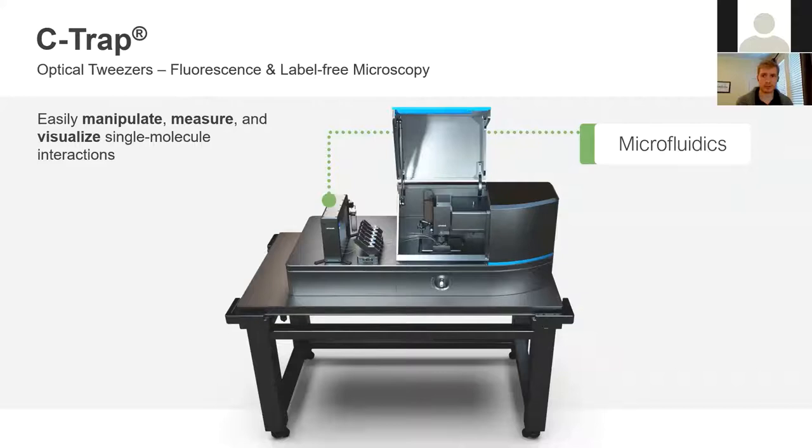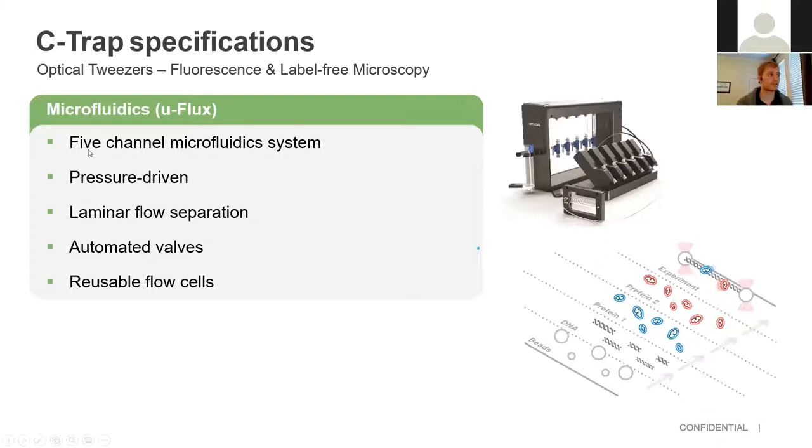The next component is the microfluidics, which we call the U-Flux. So this is a five channel system. It is driven by a pressure box. And there's no physical separation between the five channels once they enter the flow cell. They don't mix, though, because you have laminar flow separation, which I'll demonstrate on the next slide. And you can control the valves automatically through the software to decide what reagents you're going to flow in to test whatever hypothesis you have. And these flow cells are made out of glass and they can be used for months, for years, if treated properly.